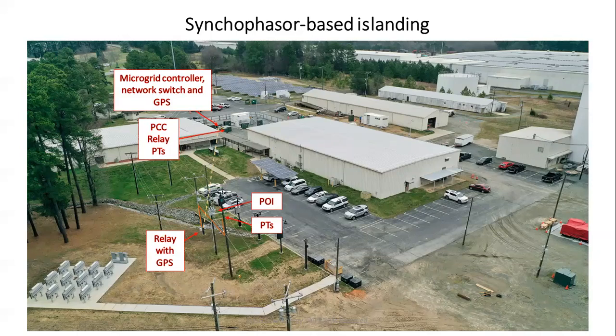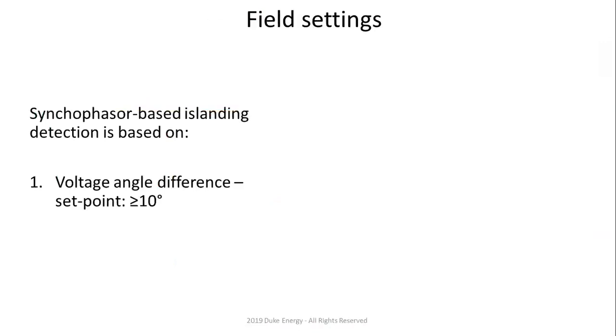And then we have a PCC over there with its own relays, PTs, and all of the GPS network control, etc. So what we did was essentially run the communications cable from the relay that is tied to the source side PTs of the POI over to the network switch where the other PCC relay is connected, and we tied all that to the microgrid controller. So once we have that, we have to do the field settings, right?